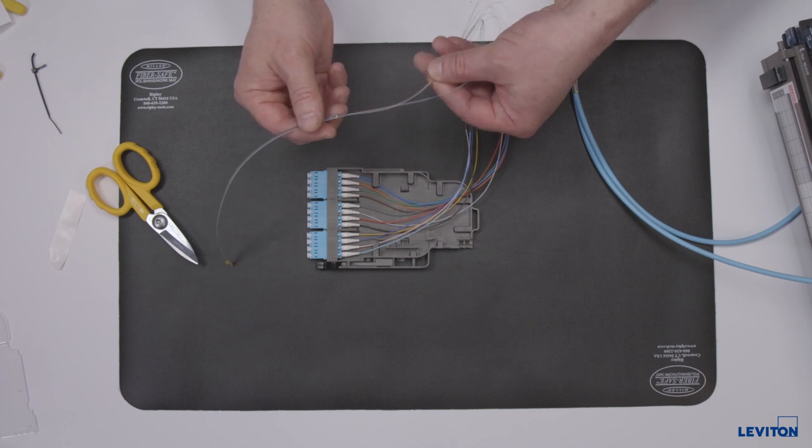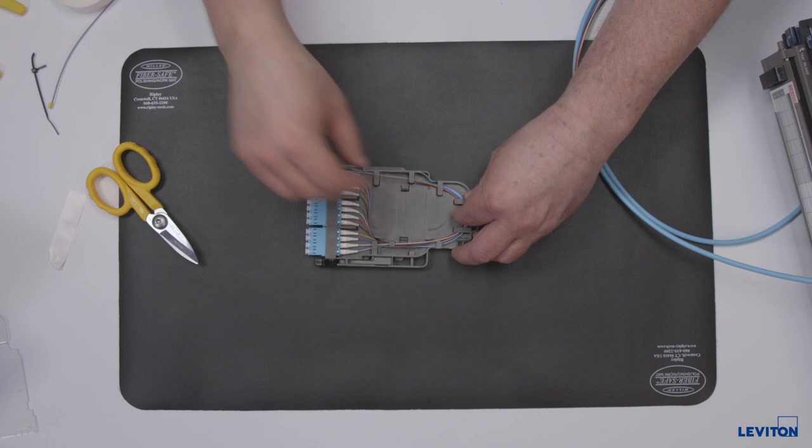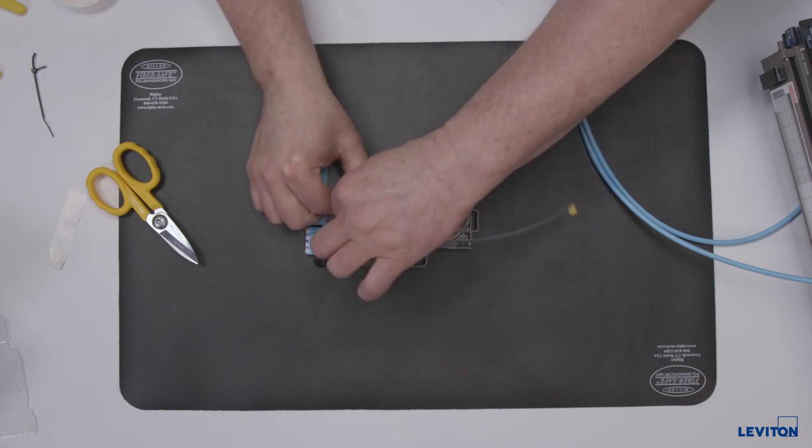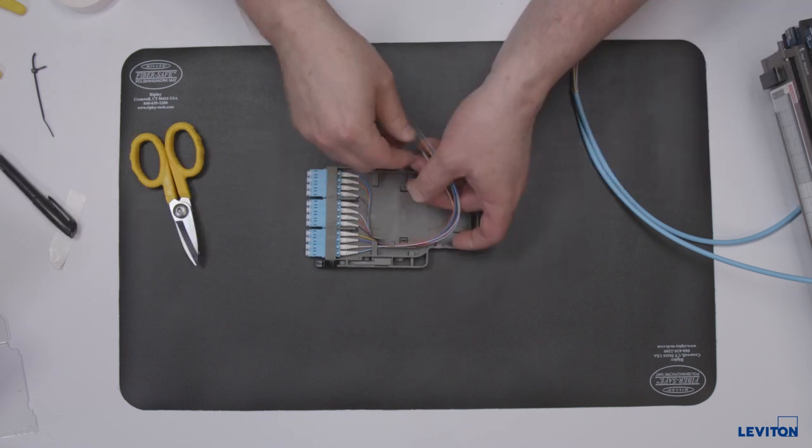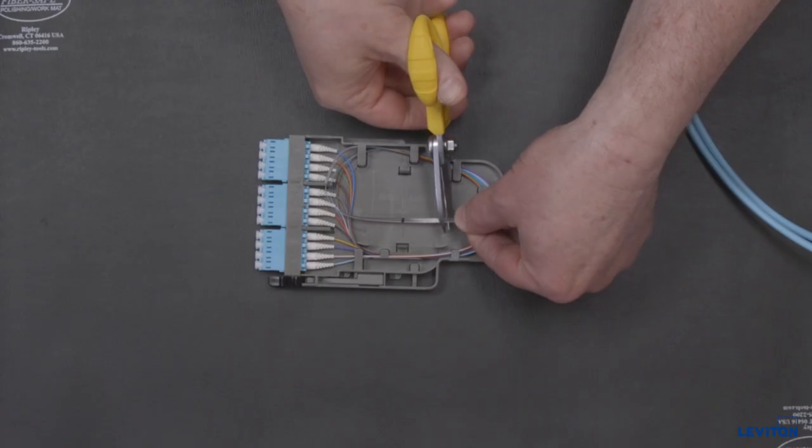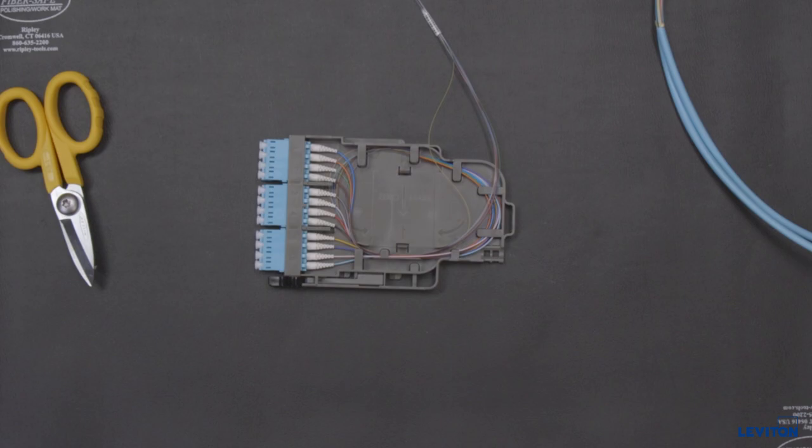If terminating to ribbon fiber, route the pigtail counterclockwise through the management tabs until all the slack is stored and the ribbon is entering the splice sleeve holder area. Mark the fiber at the zero mark guide and remove all fibers from the storage area. As an option, route the ribbon fiber through the splice sleeve holder area and cut at the far end of the holder insertion area.